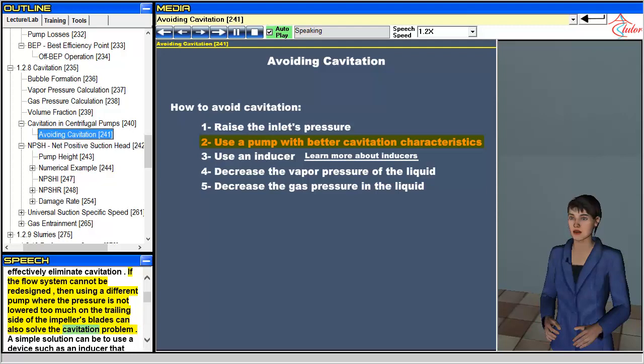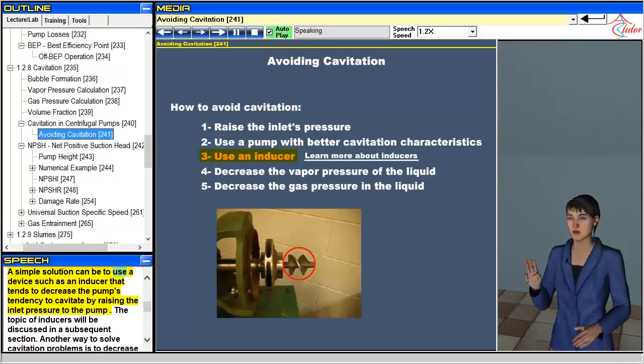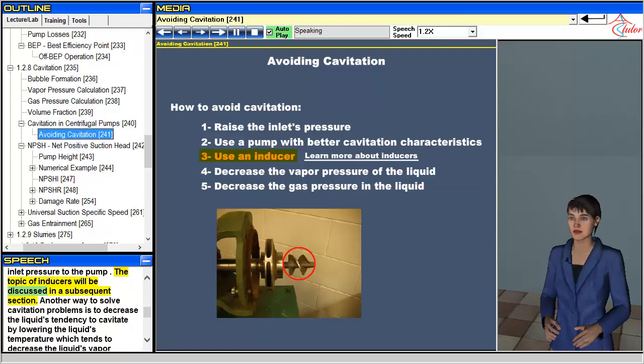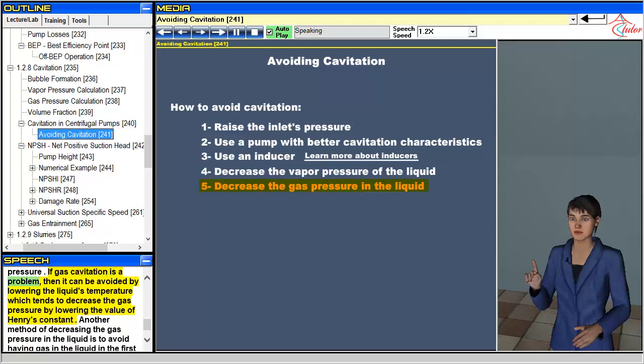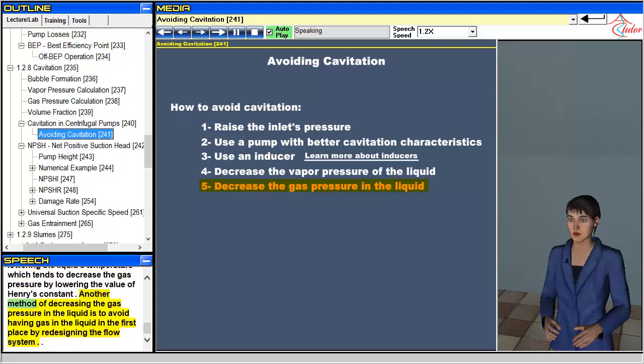A simple solution can be to use a device such as an inducer that tends to decrease the pump's tendency to cavitate by raising the inlet pressure to the pump. Another way to solve cavitation problems is to decrease the liquid's tendency to cavitate by lowering the liquid's temperature, which tends to decrease the liquid's vapor pressure. If gas cavitation is a problem, it can be avoided by lowering the liquid's temperature, which tends to decrease the gas pressure by lowering the value of Henry's constant. Another method is to avoid having gas in the liquid in the first place by redesigning the flow system.